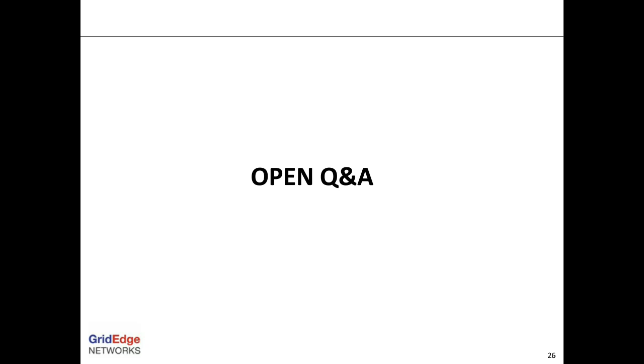Yes, I'll take this question. Thank you, Kathy. So the simple answer is, it depends. It depends on the circuit. If this is an express feeder, no RGs are required. Our longest installed system is about 20 miles long, and the longest single run is 14 miles with margin today. It's actually in Virginia. It's actually one of Jeremy's sites. So if there are no laterals or taps on that circuit, if this is an express feeder, no RGs will be required for your 17 miles.